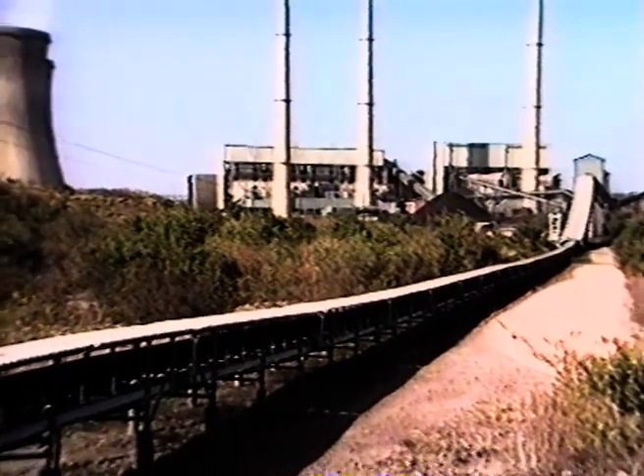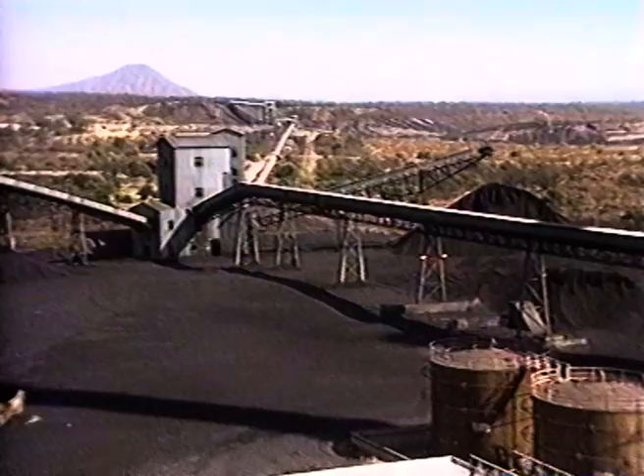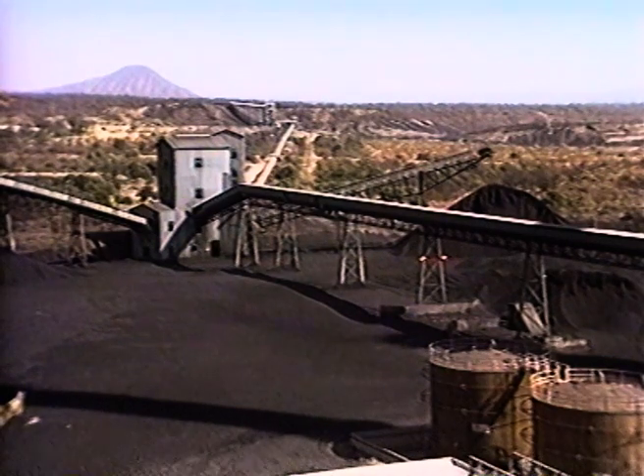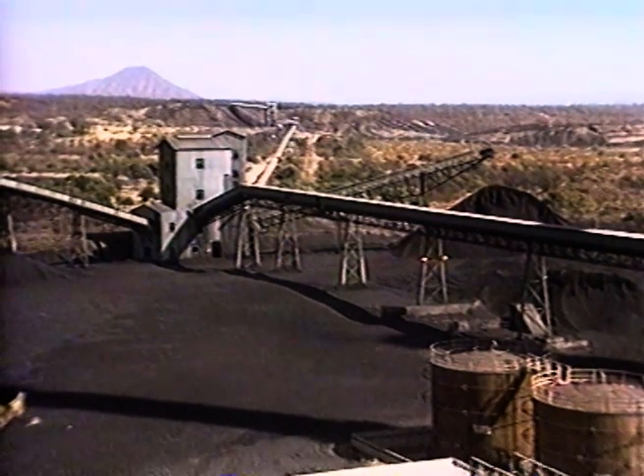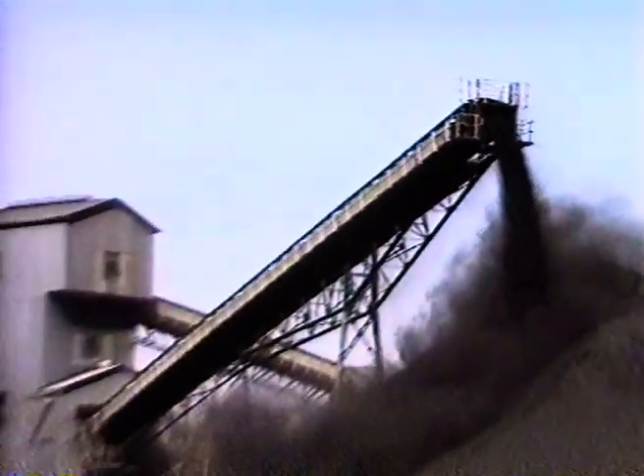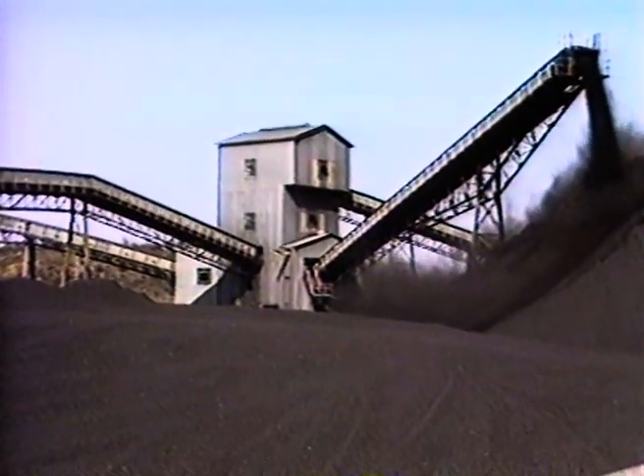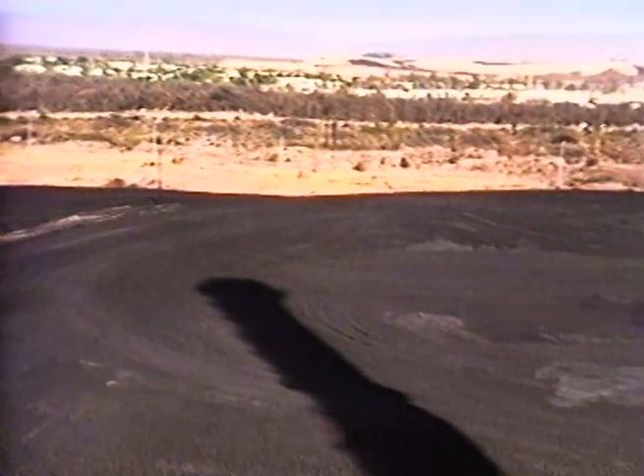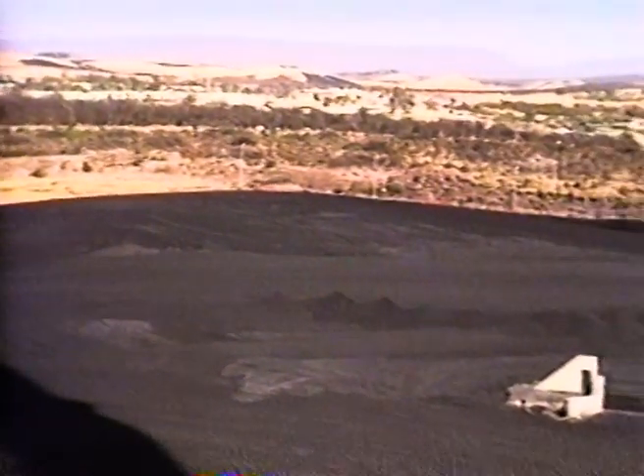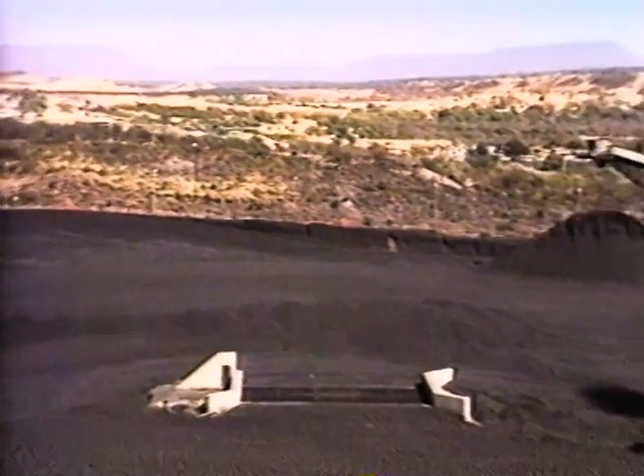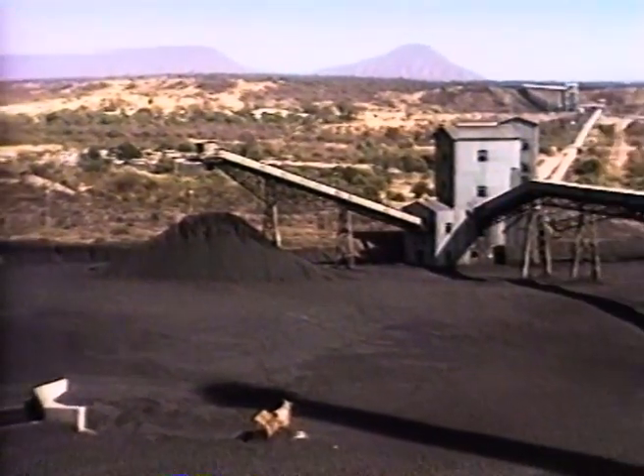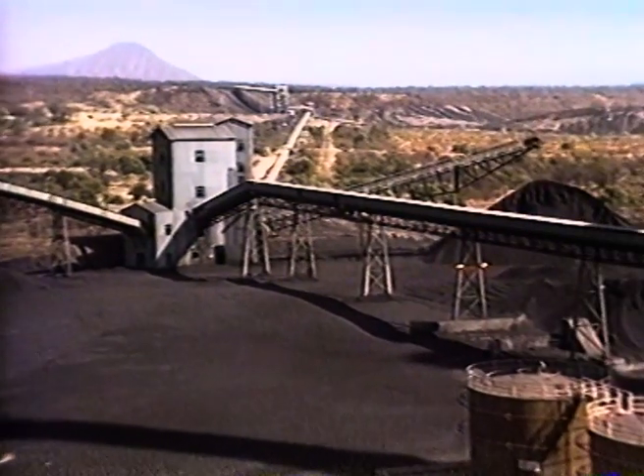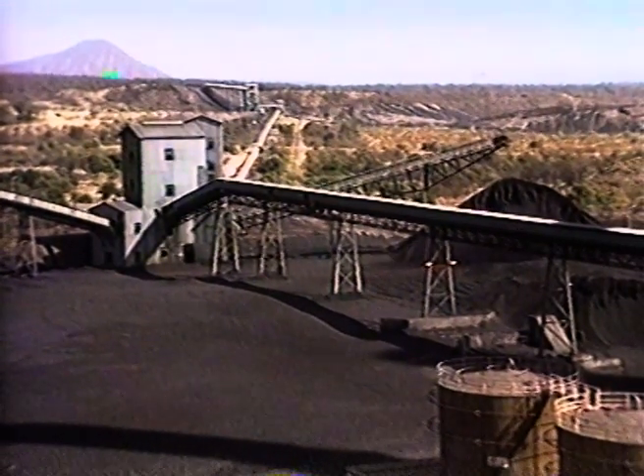Coal is supplied to the power station directly from the Hwange Colliery Company's open cast mine over a 3.5-kilometer long conveyor belt system. Almost 10,000 tons of coal will be consumed per day for full capacity of generation, and up to 450,000 tons can be stockpiled on site, sufficient for 45 days of continuous operation at full load. The coal utilized by Hwange is a very low grade, with an ash content as high as 25%, and prior to construction of the power station, this was being discarded as waste.